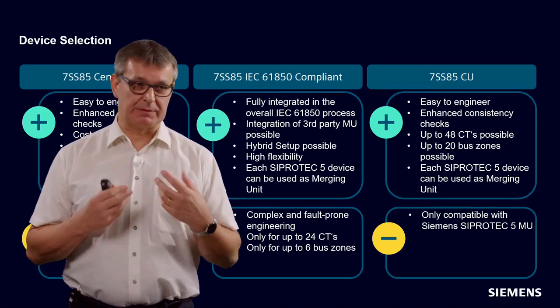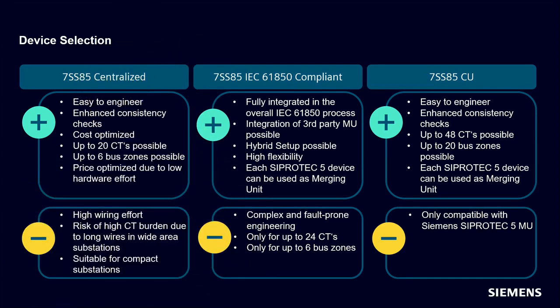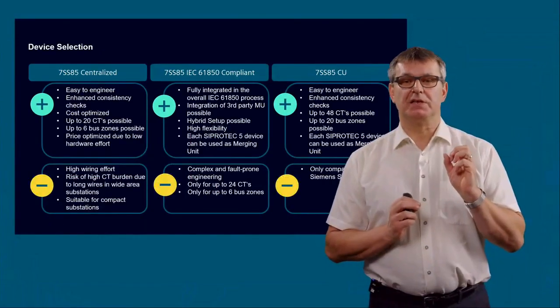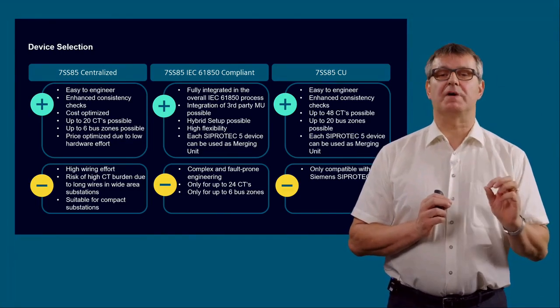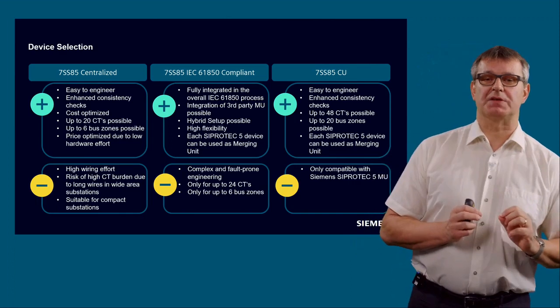If we are using a merging unit from GE or a merging unit from ABB, they have their own engineering tools, and it's not possible to integrate them with the same consistency check like our SIPROTEC 5 merging units. Up to 48, beginning with 9.40, which will be released hopefully during this week, there will be 48 CTs possible, up to now only 45 CTs. There are up to 20 busbar zones possible with the 7SS85 CU solution, and, the same as in the IEC 61850 compliant solution, you can use each modular SIPROTEC 5 device as a merging unit, as a bay unit for the distributed busbar protection. I forgot this on the slide, very important.